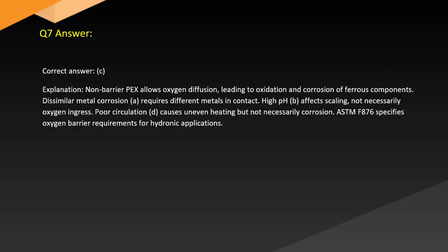Answer. Correct answer. C. Explanation. Non-barrier PEX allows oxygen diffusion, leading to oxidation and corrosion of ferrous components. Dissimilar metal corrosion, A, requires different metals in contact. High pH, B, affects scaling, not necessarily oxygen ingress. Poor circulation, D, causes uneven heating, but not necessarily corrosion. ASTM F876 specifies oxygen barrier requirements for hydronic applications.